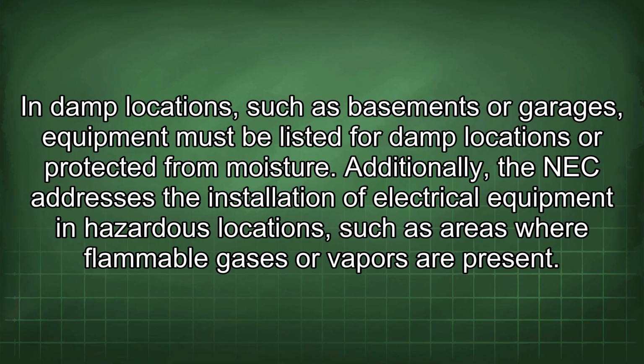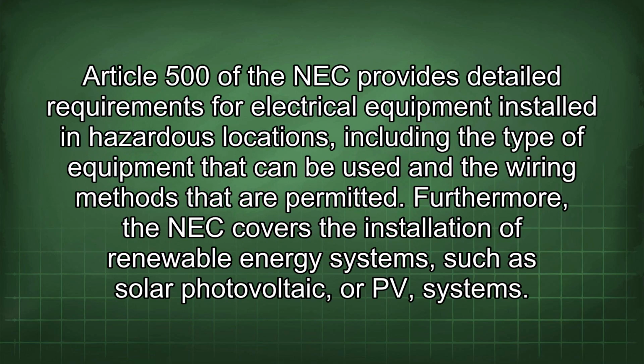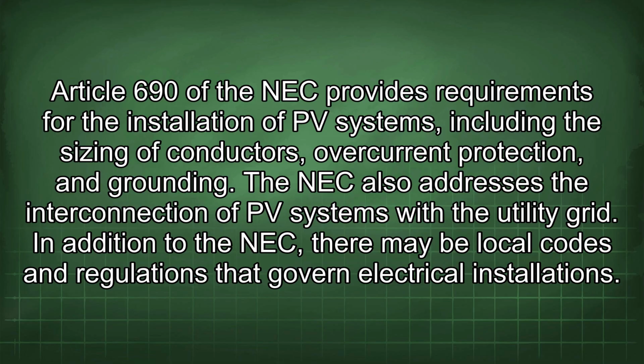Additionally, the NEC addresses the installation of electrical equipment in hazardous locations, such as areas where flammable gases or vapors are present. Article 500 of the NEC provides detailed requirements for electrical equipment installed in hazardous locations, including the type of equipment that can be used and the wiring methods that are permitted. Furthermore, the NEC covers the installation of renewable energy systems, such as solar photovoltaic or PV systems. Article 690 of the NEC provides requirements for the installation of PV systems, including the sizing of conductors, overcurrent protection, and grounding. The NEC also addresses the interconnection of PV systems with the utility grid.